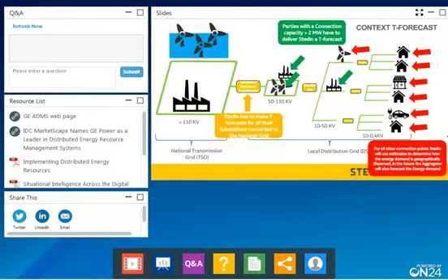So that was what we saw coming, and we combined that with an actual situation, because today the distribution system operators in the Netherlands have the legal obligation, every day, 3 times a day, to produce forecasts to the transmission system operator about the transport prognosis on the interface between the distribution grid and the transport grid. And based on that, the transmission system operator, which also has system operations responsibility, calculates whether the energy program fits into the capacity of the grid.